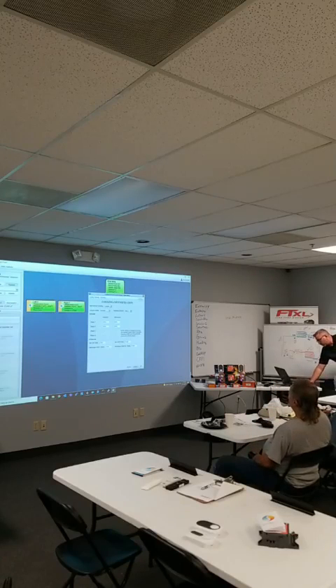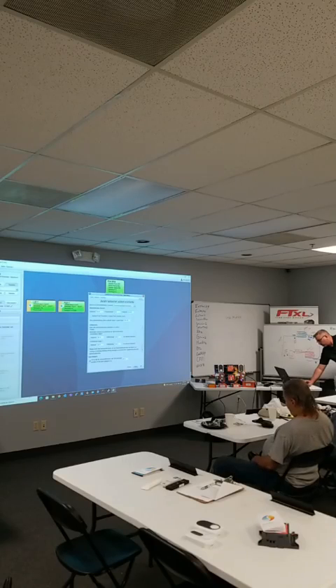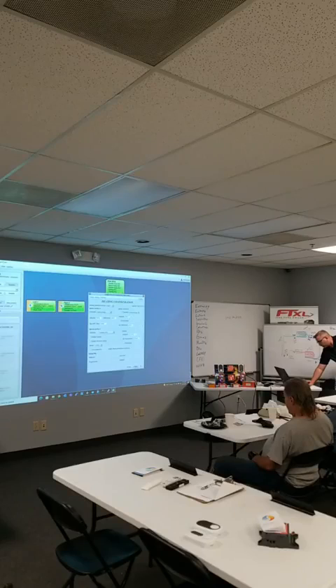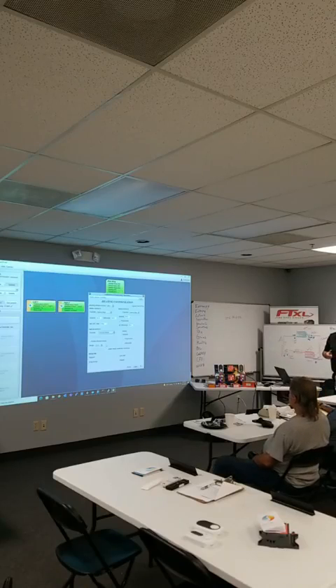So if you said to me, I want to do dehumidification, you can set up stages 1 and stages 2. If you come in here to heating, and you set this up to hot gas reheat, that output's going to kick on, but it's not modulated. It's just going to open. It's either on or off, and that's it. Yeah, on the hot gas, yep. So in this instance, you'd have W1, W2, but you'd also have a hot gas reheat.